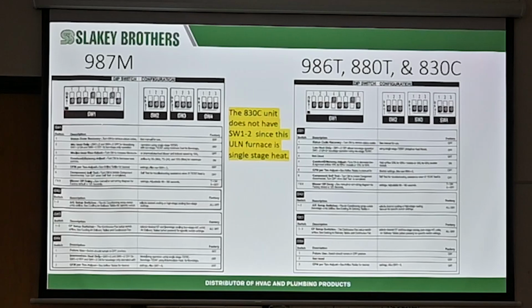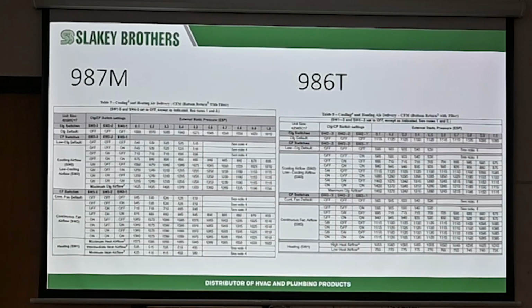So the dip switches here, SW1 on a regular thermostat, you've got to decide a couple things. Right here's the first one. Do you want to do 400 CFM per ton or 350 CFM per ton? If you want to do 350 CFM per ton, for instance, you've got to turn on number 5, and on the other ones you've got to turn on number 5 as well. And then your airflow, you're going to go through your airflow chart, depending on your unit. Again, this is when you're not using the Connex. When you're using a Connex control and you're doing a full Evolution install, dip switches don't matter. You can get in there and flip stuff around, it's not going to matter. The Connex will communicate and tell the system, I have a so many tonnage outdoor unit, I want 350 CFM per ton, this is what I want you to do. But with the non-Connex, go through the dip switches and set up your airflow.